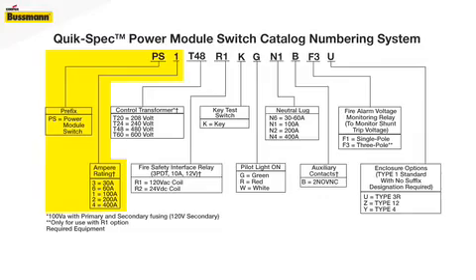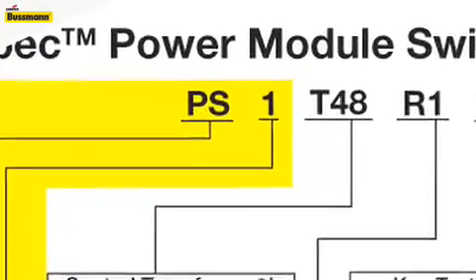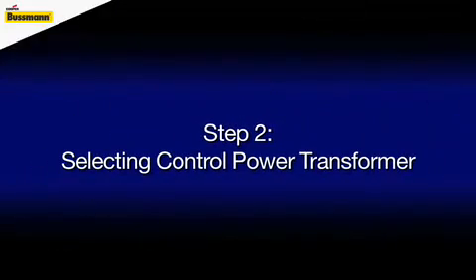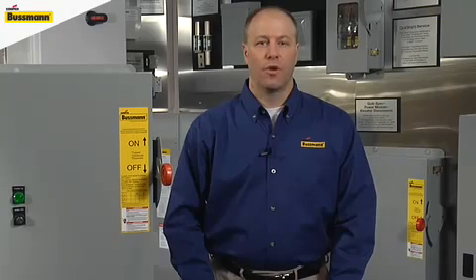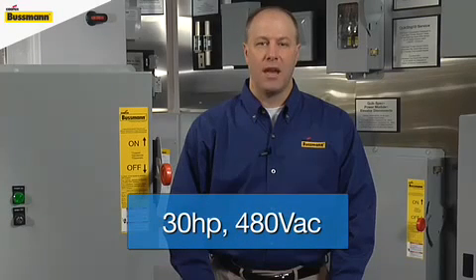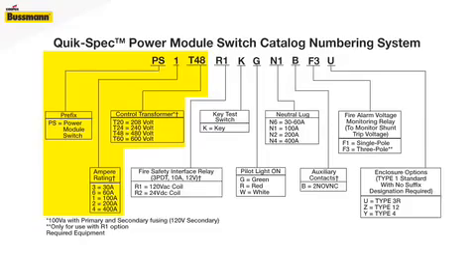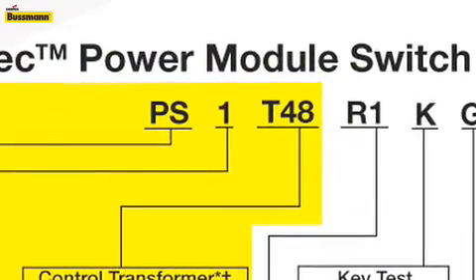The correct selection in step one of building a part number for the power module switch would be PS1. The second step in the process is the selection of the proper control power transformer. Continuing with our 30 horsepower rated 480 volts AC example, the correct choice would be a T48, which stands for a 480 volt AC incoming service.